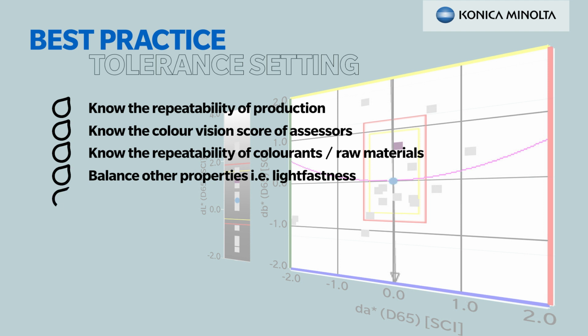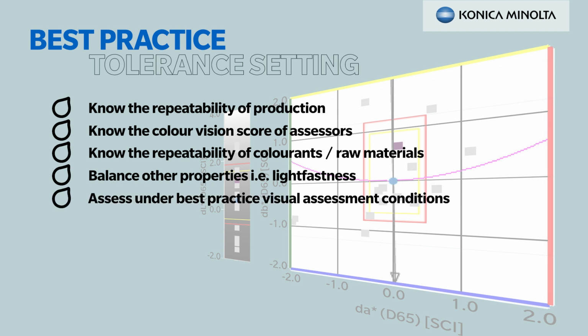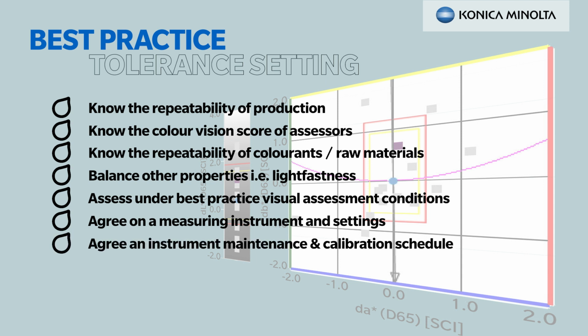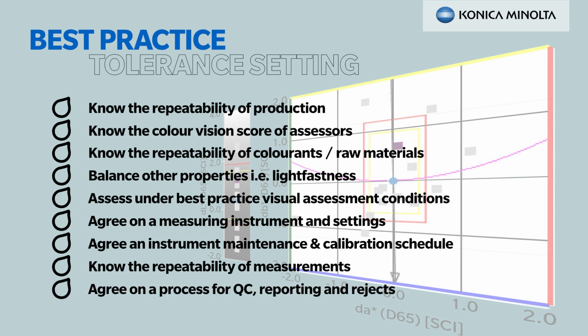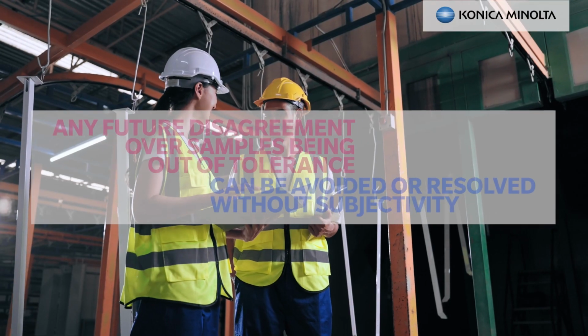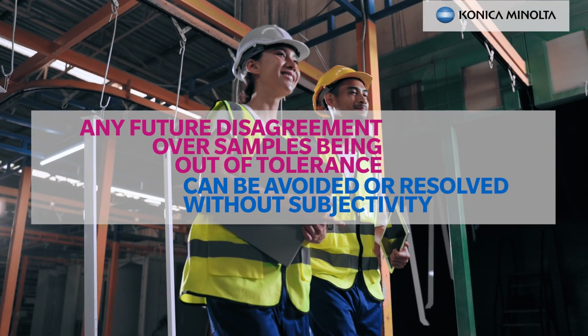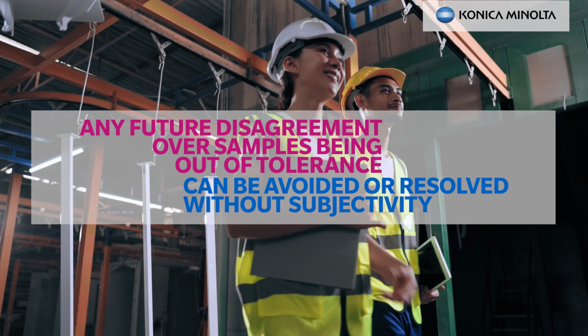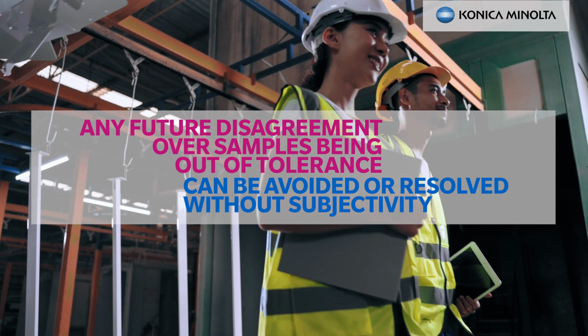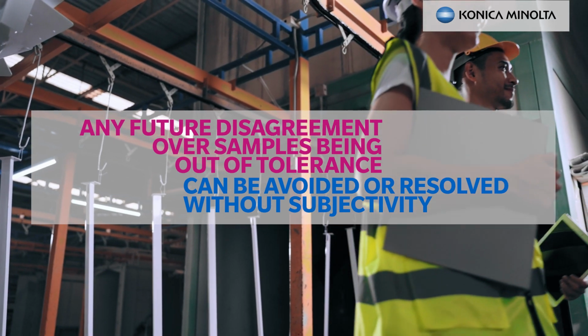You should operate under best practice visual assessment conditions using a light cabinet, angle table, and probably more than one illuminant. You should agree on an instrumental measuring solution, the approach for measuring, and a maintenance schedule. You should know how repeatable measurements are, especially if the product has a complex surface. You should agree on a process for rejects and QC. This way, any disagreement over samples being in or out of tolerance in the future can be avoided or resolved without subjectivity.